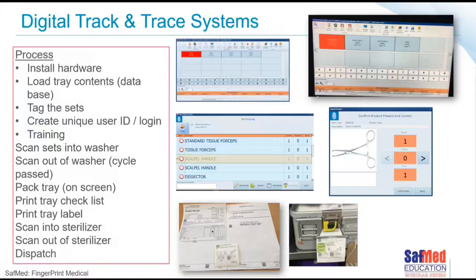Now I'm going to wrap my set. Once my set is wrapped, obviously I can no longer scan the tag. So now I need a label, a batch label. So of course the computer will print for me a batch label as well. Checklist in the tray, wrap my set, and I stick my batch label on the outside. That batch label is unique to that particular set.